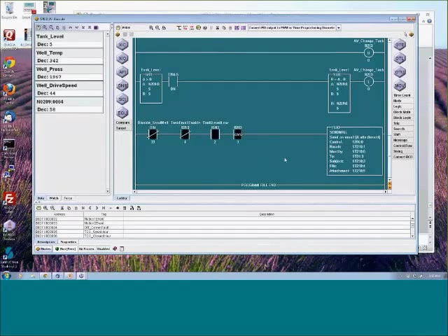So this is the PLC Ladder Logic. Those of you that know Allen Bradley PLCs can see that it looks very much like an Allen Bradley PLC. I'm going to go to this program, and down here what we're saying is when the tank level is low, we're going to send an email, and that's what this little subroutine does.